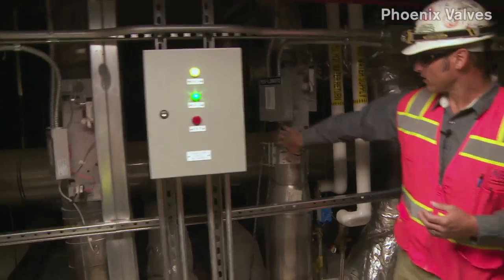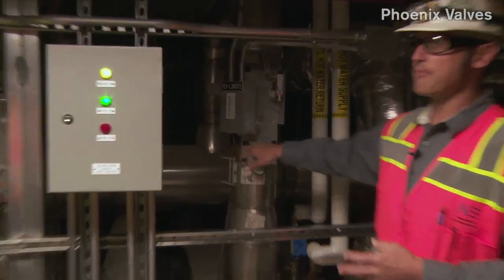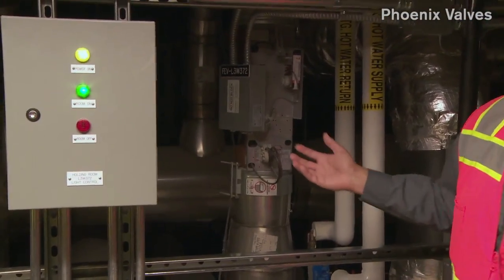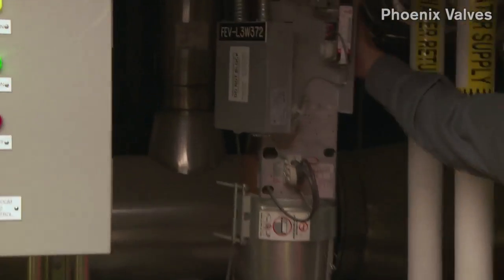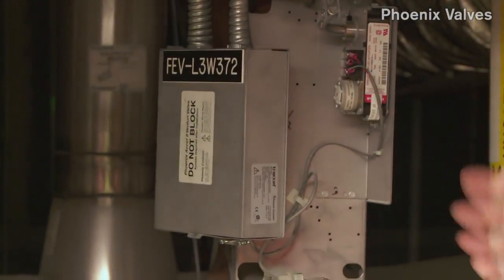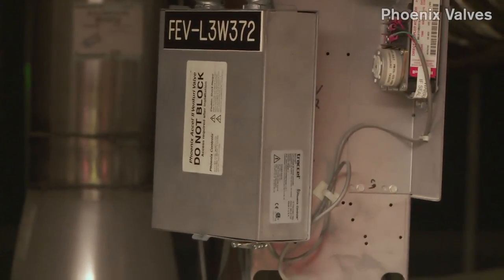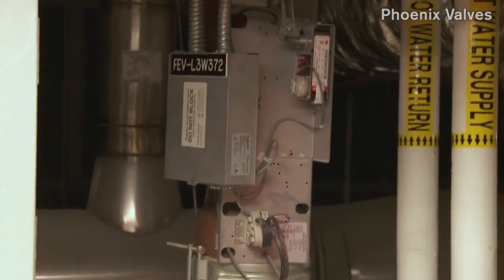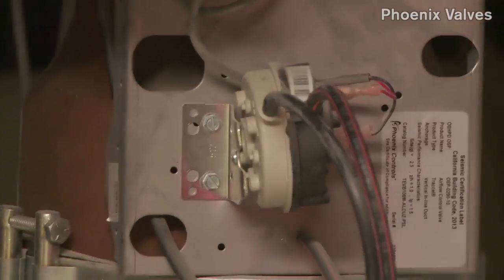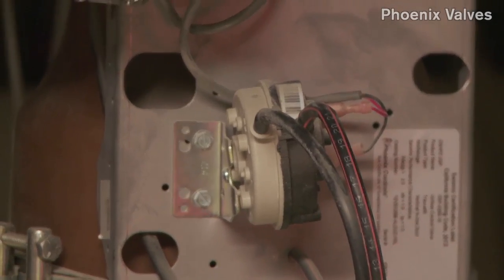We also have our coated valves that are more for hood applications or biosafety cabinets. Whenever you put any type of chemicals in there, you want this coating on here that's going to protect the valve and not be so corrosive. It also has the pressure switch. It has its own controller board on it. It's receiving signals or whatever we program it to be. If it's a constant volume, we directly put the values in there.